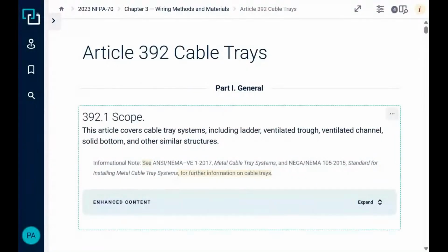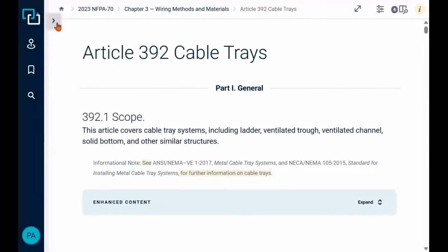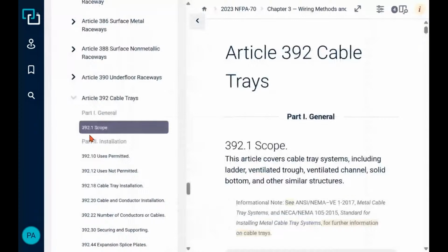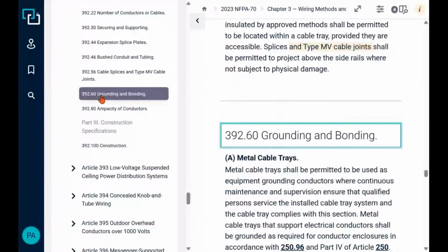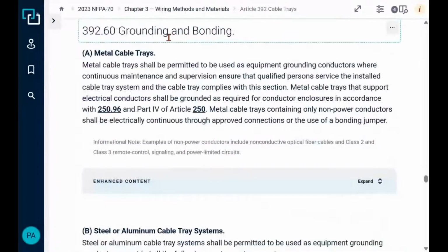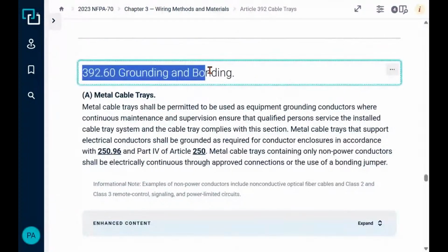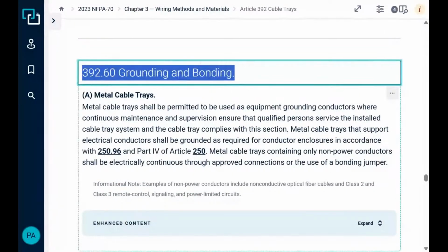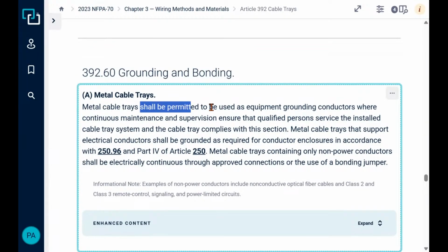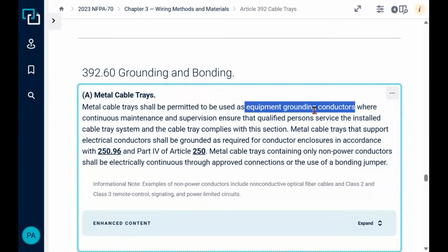just to show you what it says. And let me jump down here really quickly. Let's pull back. So this is 392.60 right here. Okay. So this is in 392. And it's talking about, again, the metal cable tray. It makes sense. That's what we're focusing on. It says metal cable trays shall be permitted to be used as equipment grounding conductors. Not required. It's permitted as long as you meet all the other rules you have to meet, right?